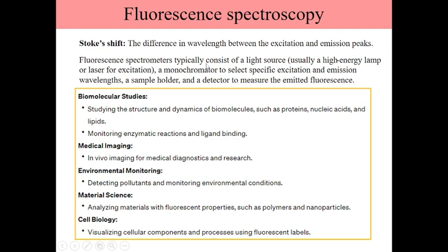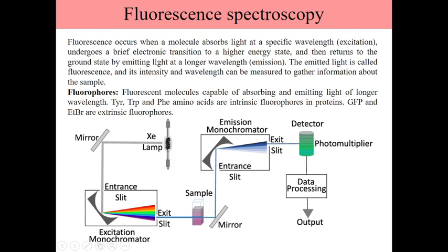So the applications of fluorescence spectroscopy. The fluorescence spectrophotometer is the device, you saw it, and it is different from the absorption spectrophotometer in this particular aspect. Firstly, the sample and the monochromator or the detector are present at right angles to one another. That is point number 1. And the second point is this particular emission monochromator, which is an additional thing in the fluorescence spectrophotometer.